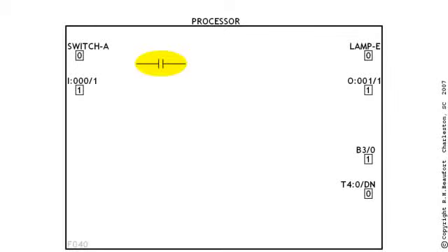And one more. When the processor comes to this XIC instruction in the program, the rule says that he's got to go look for a 1. The address tells him that he's going to look in the bit box named T4:0/DN. Many students already know that this is a timer's done bit, but to the XIC, it's just another box. The main thing is that the PLC processor doesn't know or care about what the bit means. He's just looking in a box for a 1. It really is just as simple as that.